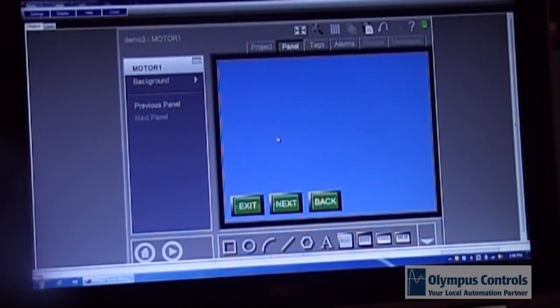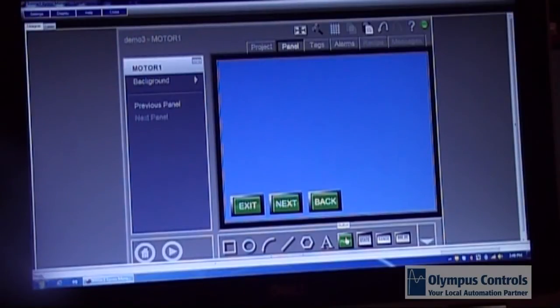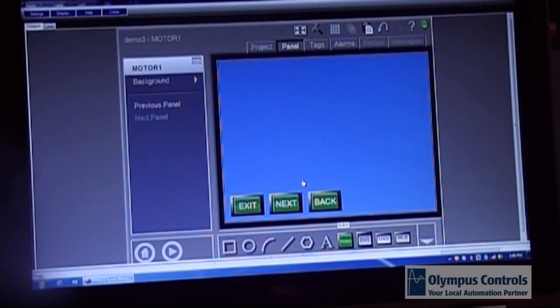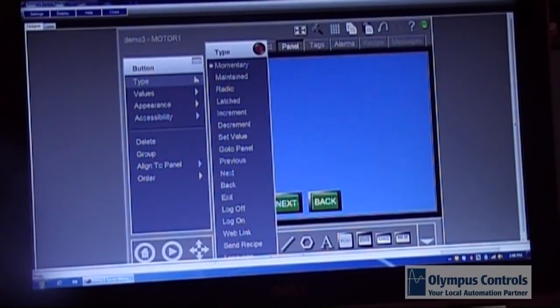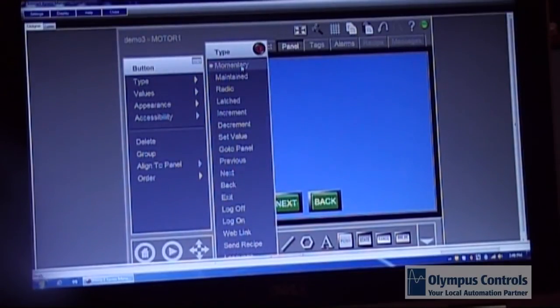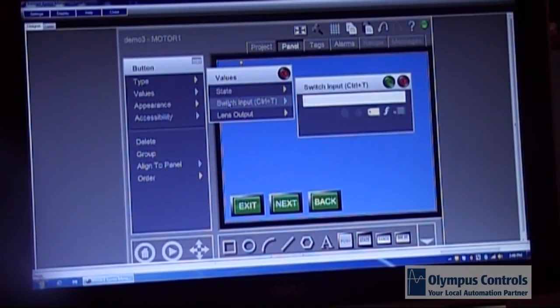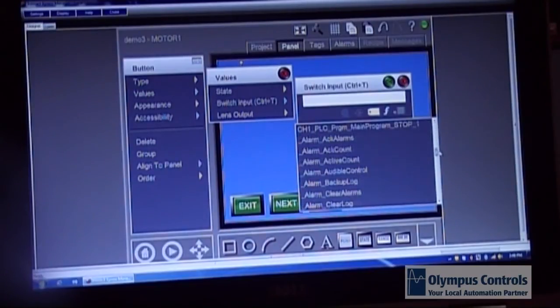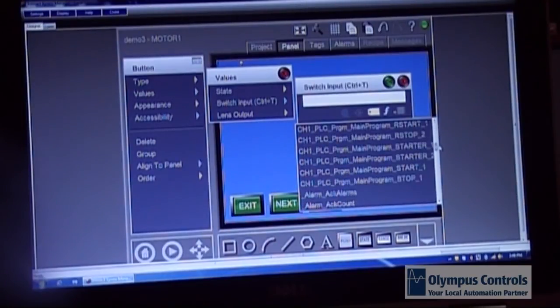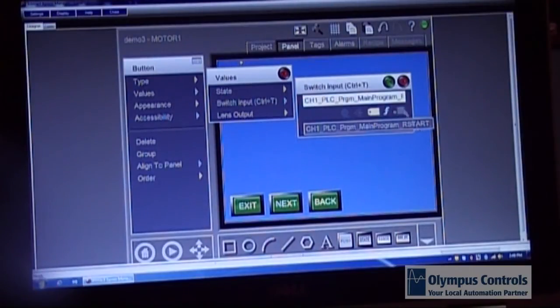Now that we've finished creating our program control buttons, I'm going to get into creating some buttons that use the tags in the PLC. First I'm going to create a start stop button. So you choose momentary. You have to choose the switch input. Use the tag icon. Pick the tag out of the PLC that's associated with the start button. And click OK.